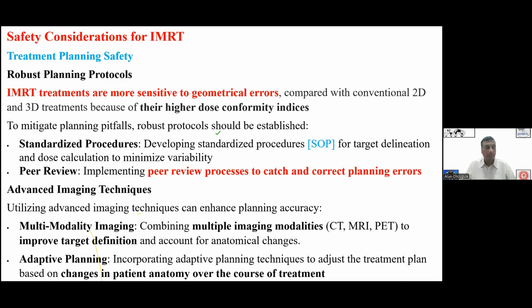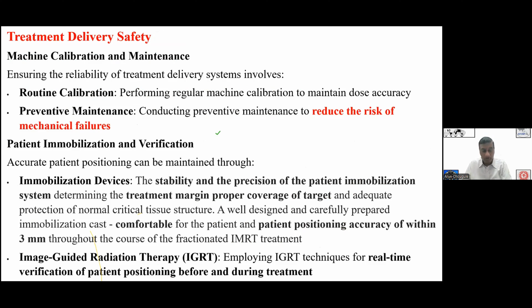Routine calibration and preventive maintenance reduce the risk of mechanical failure. For immobilization devices, the stability and precision of the patient immobilization devices are very, very important. They should be comfortable at the same time. So these are many, many things we have to take into account. Day-to-day position changes in the target volume: for some cancers such as prostate, bladder full, rectum full, all those things we have to take into account, because when you treat the prostate, the bladder should be full or empty consistently. There are major challenges in treating tumors in cardiothoracic regions and the pancreas, where organs move during treatment. Adaptive treatment, interfraction target position changes, and setup error can be minimized by IGRT and all those things.